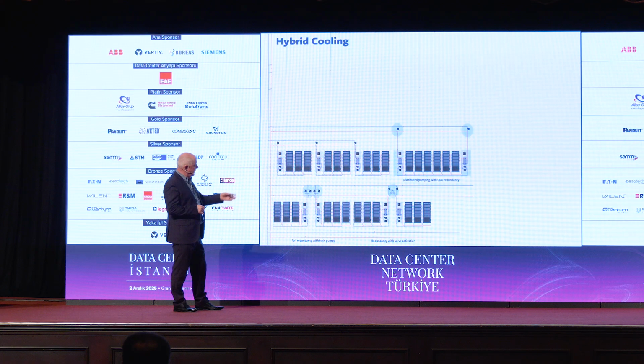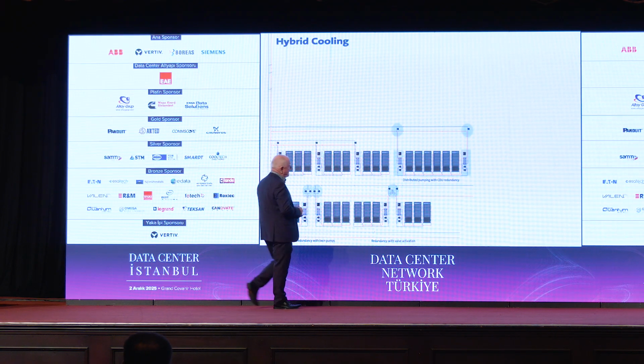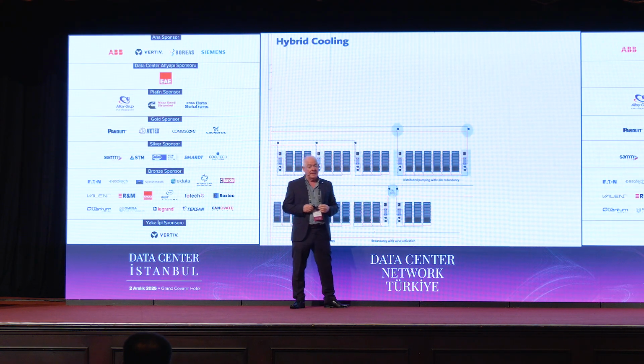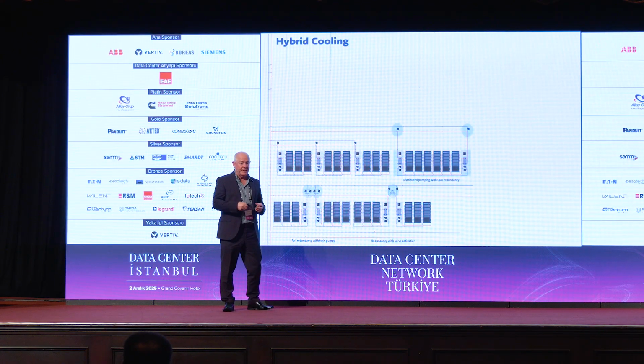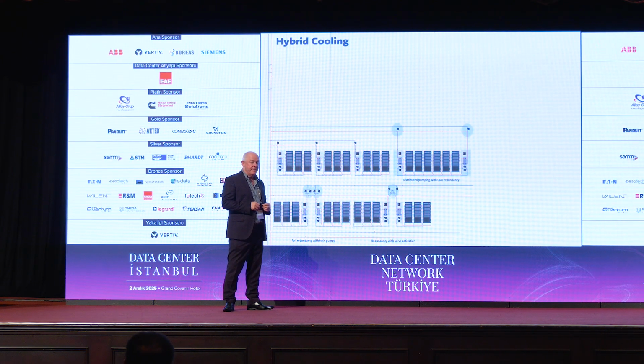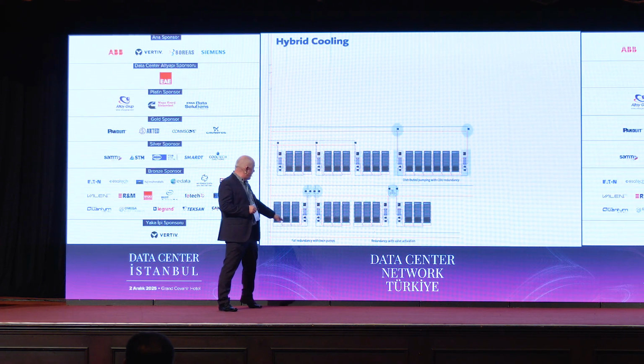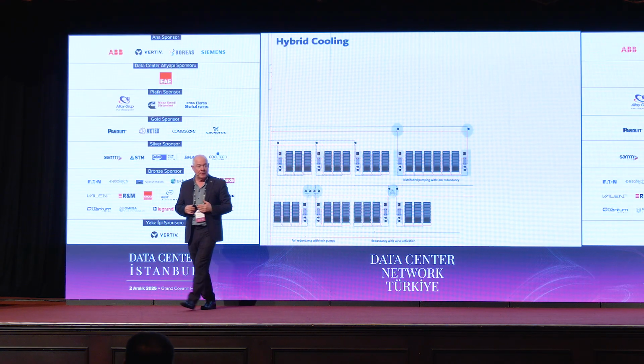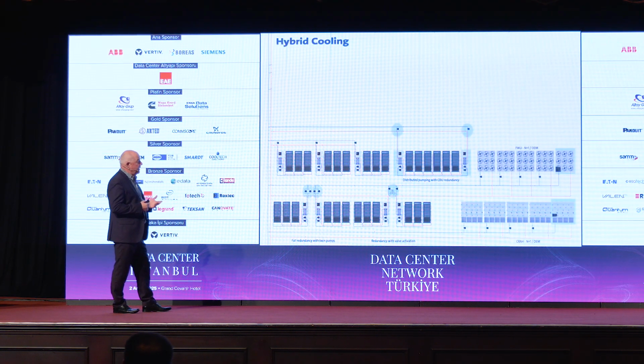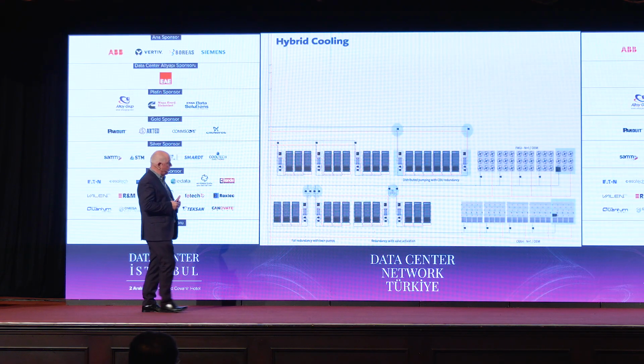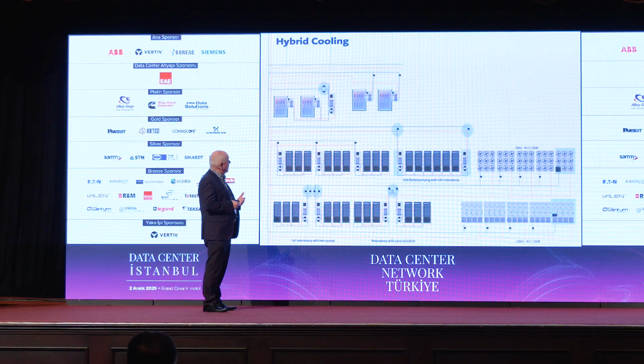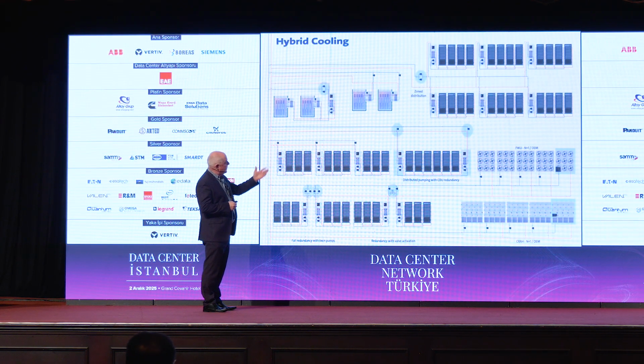We don't have redundancy on this one, whereas over here we've got some CDUs and we've got redundancy built into the CDUs. So we've one redundant CDU for the rack system. And the CDUs will generally have twin pumps in them. That's the way they've been designed and manufactured. If we look at fan walls and CRAH units, we'll generally have N+1 or N+2. So we've met our redundancy that way as well. It's built into the whole system. Or we can go for zoning as well, where we've got twin pumps meeting a complete zone.